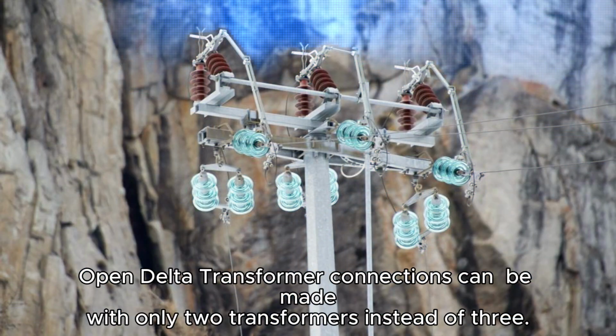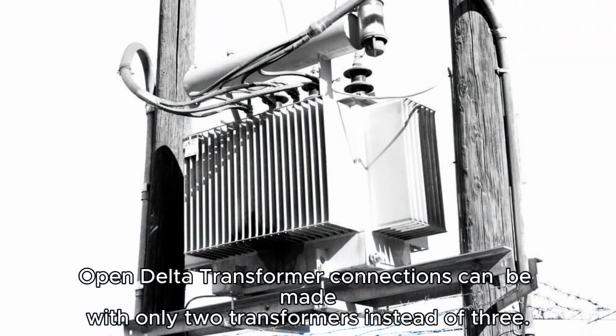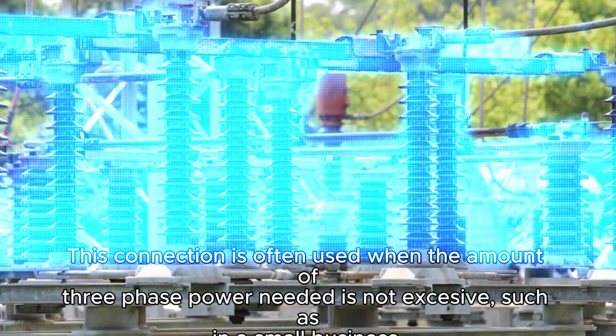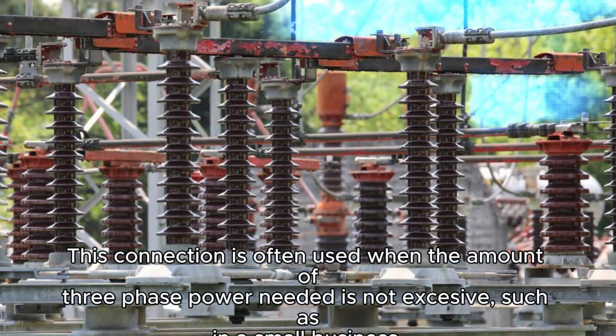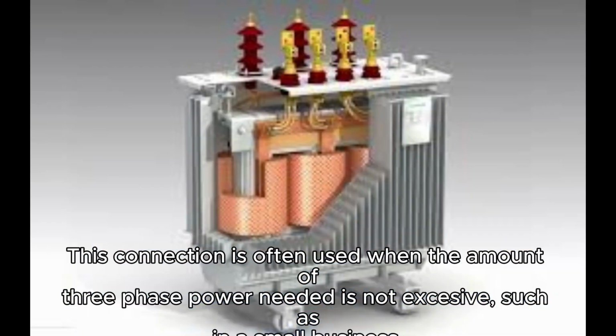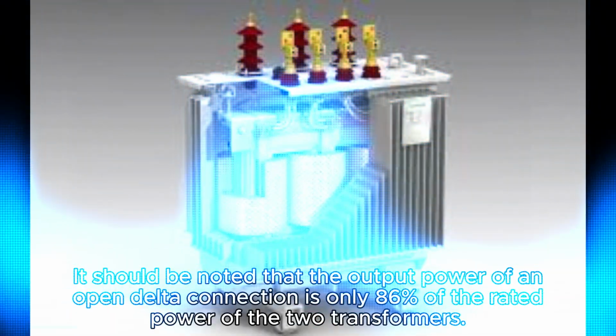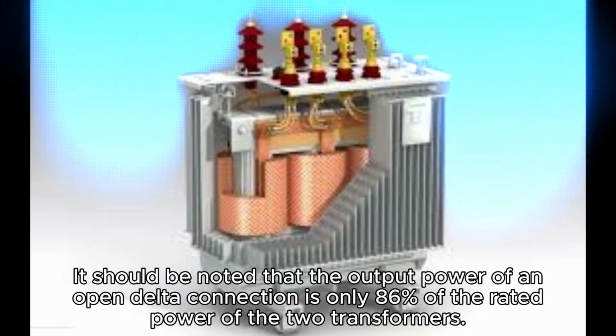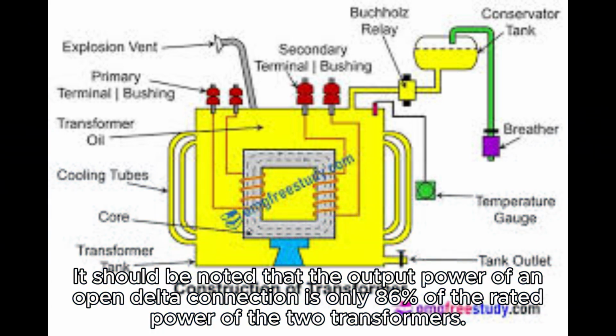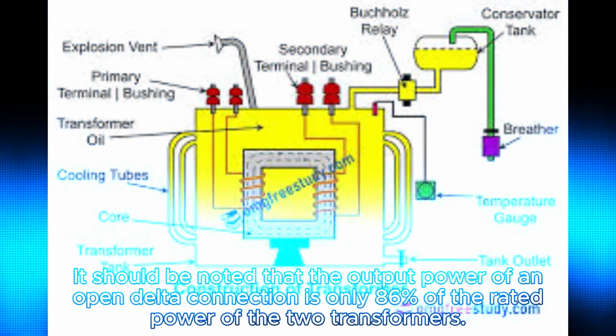Open delta transformer connections can be made with only two transformers instead of three. This connection is often used when the amount of three-phase power needed is not excessive, such as in a small business. It should be noted that the output power of an open delta connection is only 86% of the rated power of the two transformers.